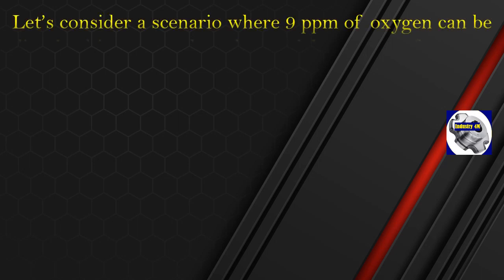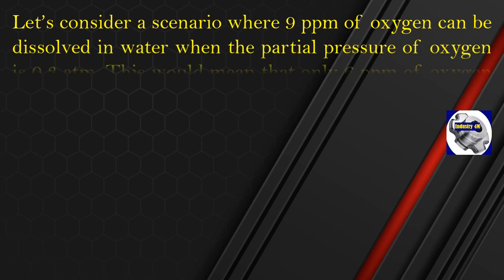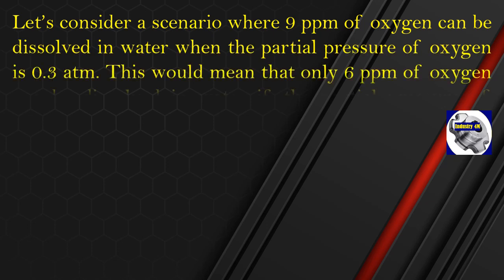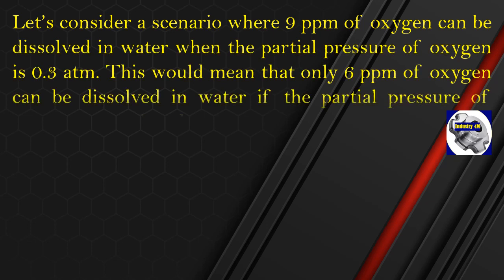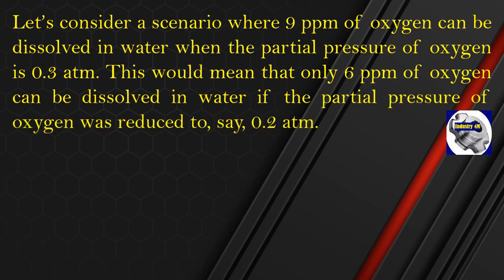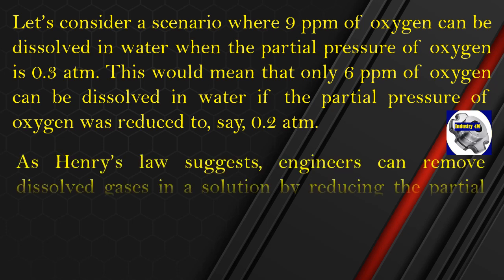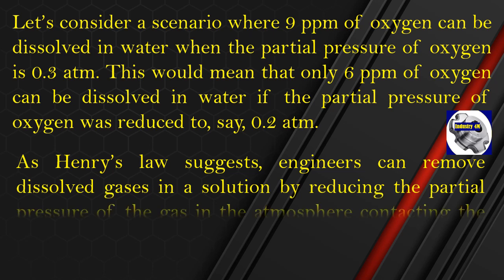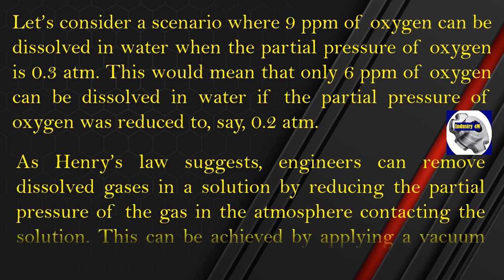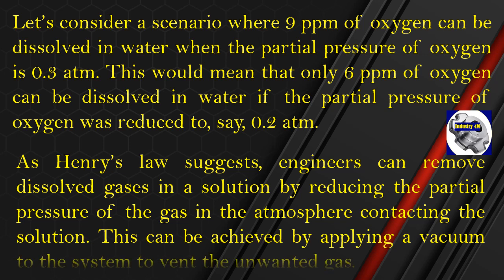Consider a scenario where 9 parts per million of oxygen can be dissolved in water when the partial pressure of oxygen is 0.3 atmospheres. This means that only 6 parts per million of oxygen can be dissolved if the partial pressure is reduced to 0.2 atmospheres. As Henry's Law suggests, engineers can remove dissolved gases in a solution by reducing the partial pressure of the gas in the atmosphere contacting the solution. This can be achieved by applying a vacuum to the system to vent the unwanted gas.